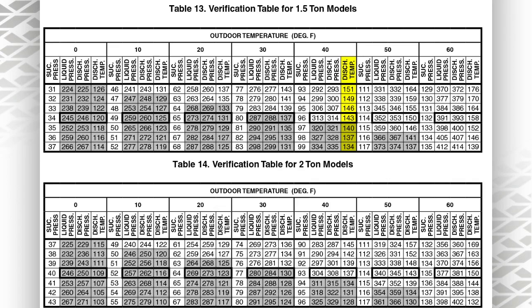Again, I will also tell you this. Don't use a heat pump heating chart to charge a unit. If you've got a problem with the charge or the unit's not working right, I'm always going to recommend that you recover all the refrigerant out of the system and you weigh the entire charge back in, and that way you know that charge is right. Because in the heating mode on any heat pump system, a lot of that charge is stored within the system. You use the heating charging chart just to verify the unit is functioning.